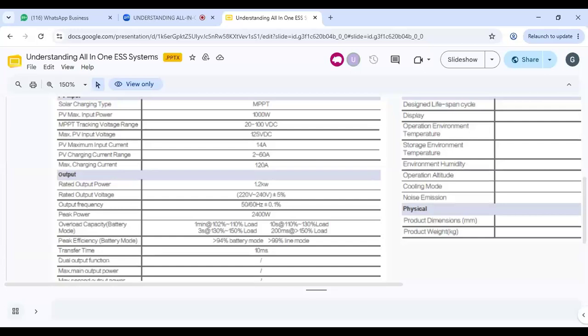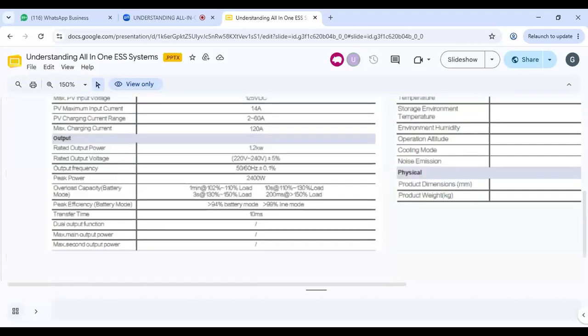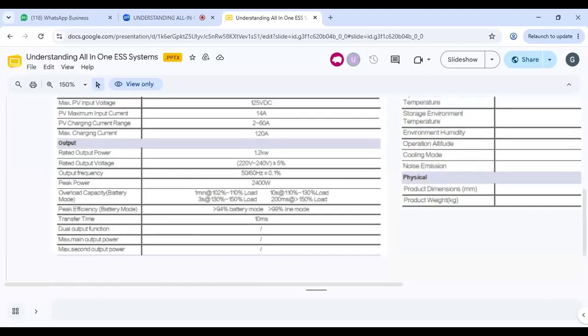14 amps is the maximum current that can flow through the solar cable into the charge controller. That's the maximum it can accept from this. If it's more than that, it's not going to take it. It will only take 14. But then, the one that will now go to the battery is 60 amps max. So then look at the other part of it.